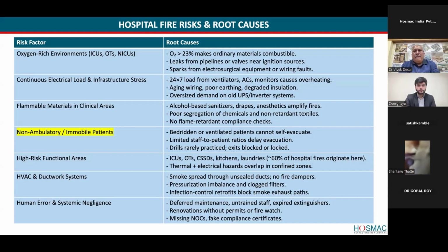Yes. So, as Dr. Desai has explained, all the 24 by 7 electrical load has to continue in the hospital because of the criticality. So when the load is 24 by 7, one has to take care of the electrical safety by taking a lot of safety factor. Like normally we take 20% safety factors. So whatever the kilowatt is, there will be a full load ampere. So one has to take the ampere loading into consideration, and all the derating factors for all the wires and switch breakers have to be there, while designing especially the medical equipment power supply and the HVAC power supply. So when you take derating factors into consideration, it includes all the continuous load, because the continuous load is happening, there will be continuous heat generation over a period of time, and the wire gets deteriorated. So all these factors are considered, so that short circuit etc. will not happen.